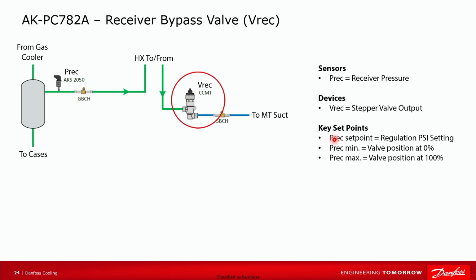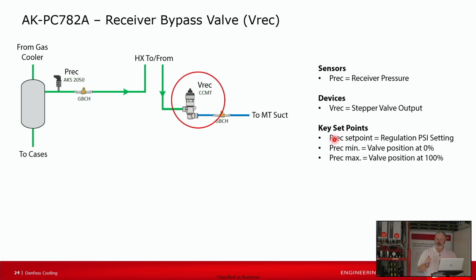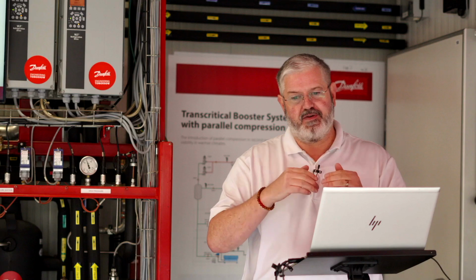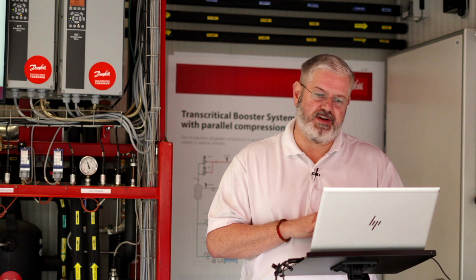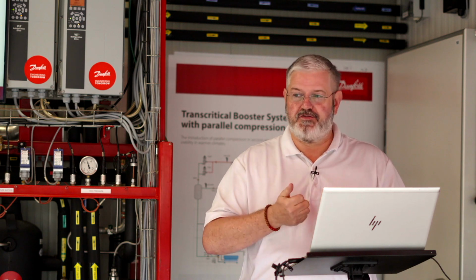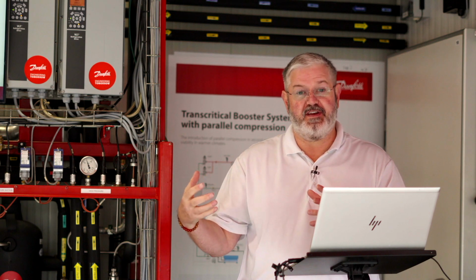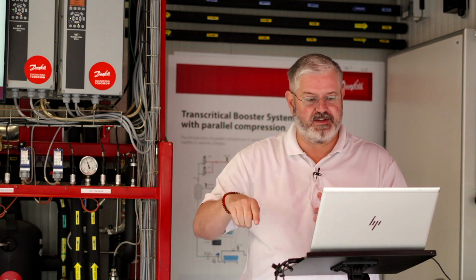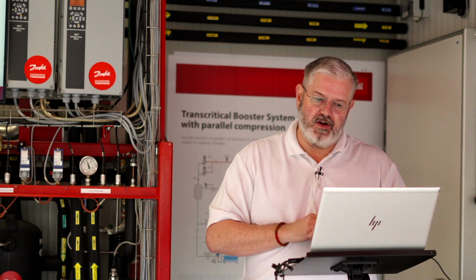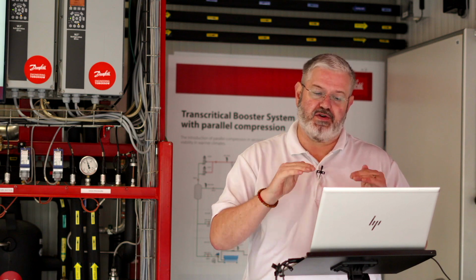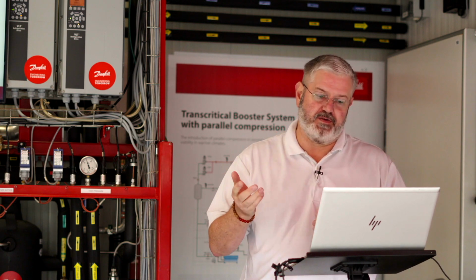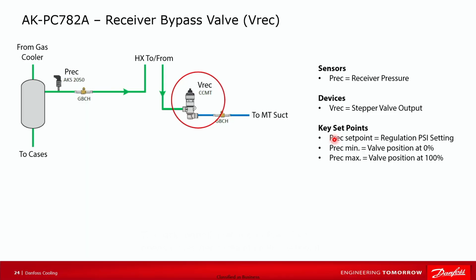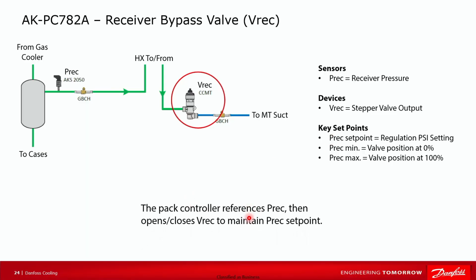One difference between the receiver valve and the high pressure valve is that the high pressure valve will never be fully closed or fully open. If you fully closed it, that's a dead stop, and you're going to pretty quickly trip the high side of the system on high pressure. If you fully open it, you're going to trip your low temp compressors, because you're just sending all the flow through, especially on a hot day. This valve, however, will close completely if it needs to build pressure in the flash tank, and it will open to 100% if it needs to relieve pressure from the flash tank. So it references the receiver pressure transducer and just does its thing.